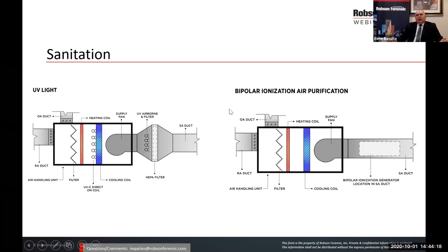So what are we looking at? Sanitation, comparing both of these items. And I put the graphic up here so I can explain how they work and where they work, right? So this is the outside air coming into the air handling unit. This would be the return air from your space. These two mix in here. Hopefully there's enough outside air coming in to afford a viable dilution inside the space. That's filtered out, whether it be a MERV 13 or higher or lower, if your unit can't handle it. It goes through a heating coil and will have the UV light, UVC light, hitting the cooling coil, which is where the bacteria tends to accumulate because of the moisture in the cooling coil.